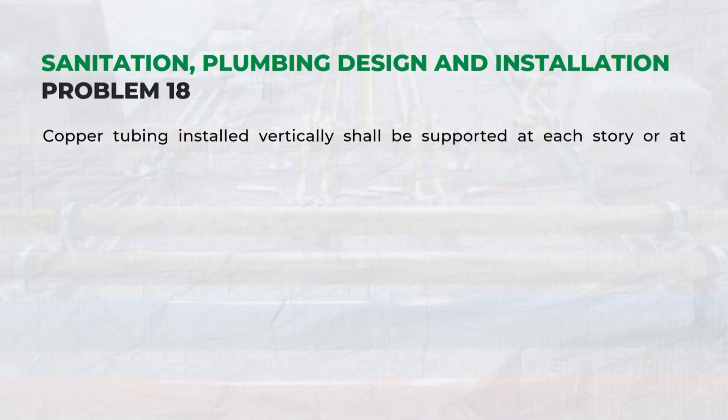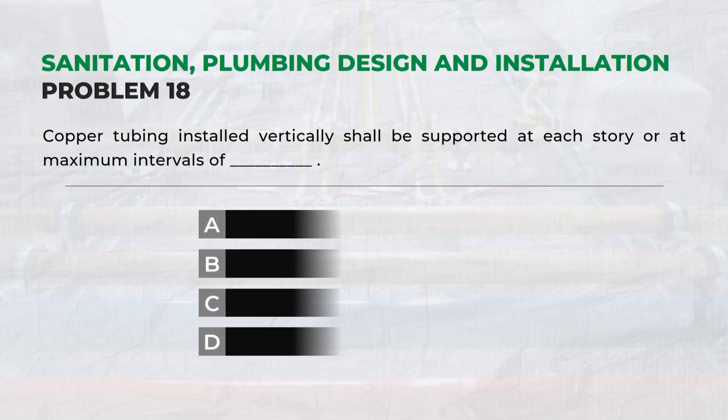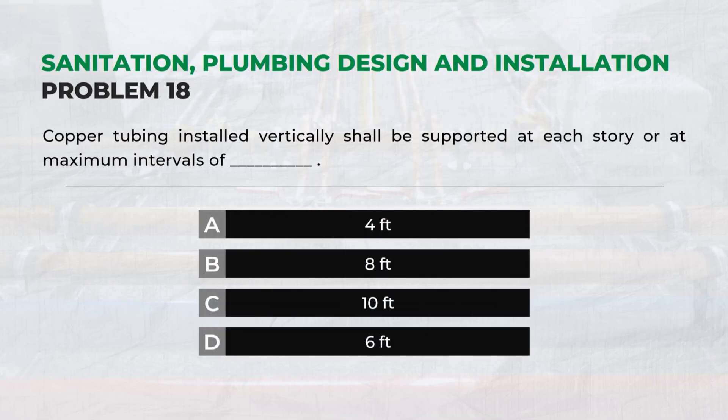Copper tubing installed vertically shall be supported at each story or at maximum intervals of: C. 10 feet.